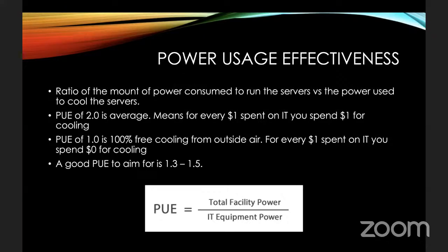However, for most of us who don't have the budgets and are constrained by the natural environment of where you are, for example in Indonesia, you're never going to achieve that kind of level of PUE. But you could aim for a PUE of somewhere around 1.3 to 1.5 if you have proper management and containment.